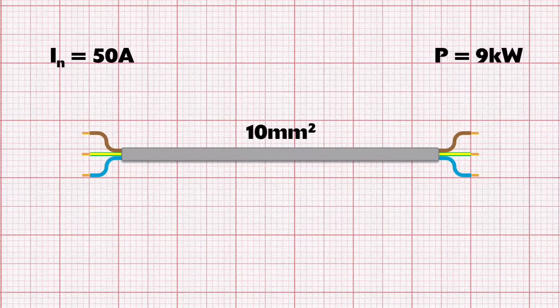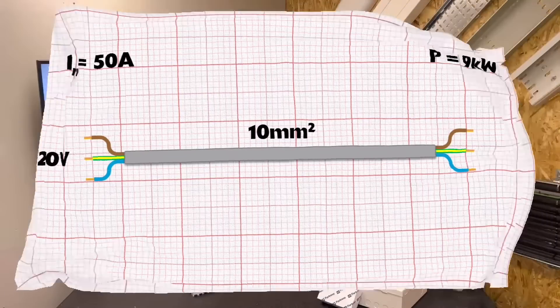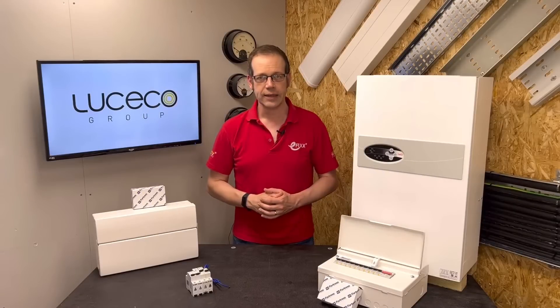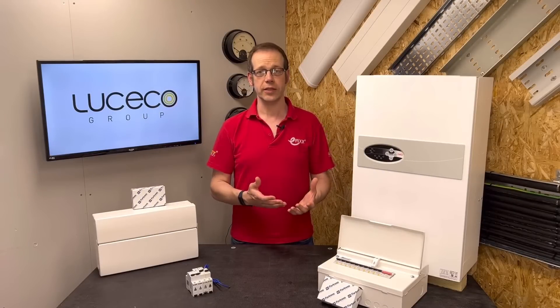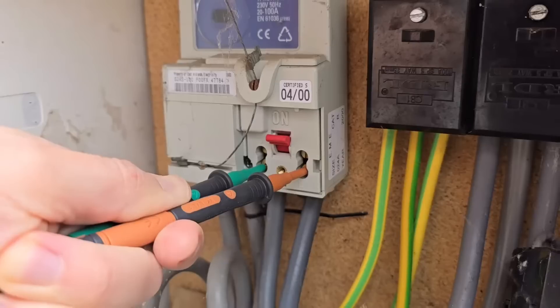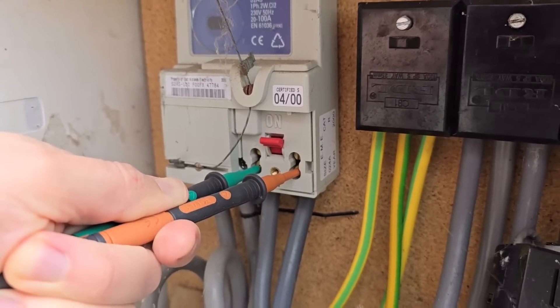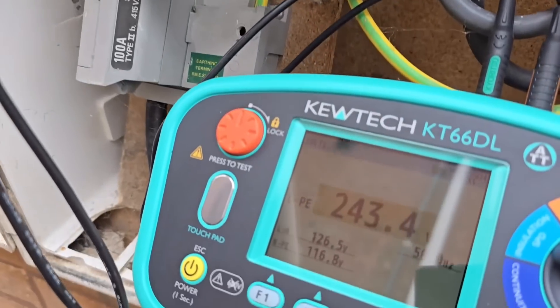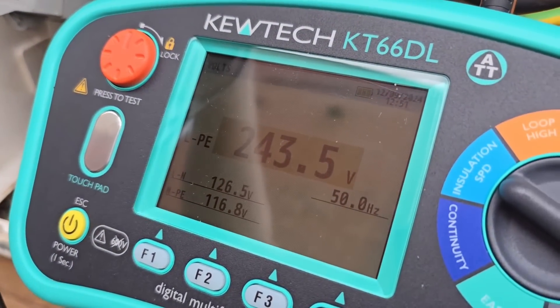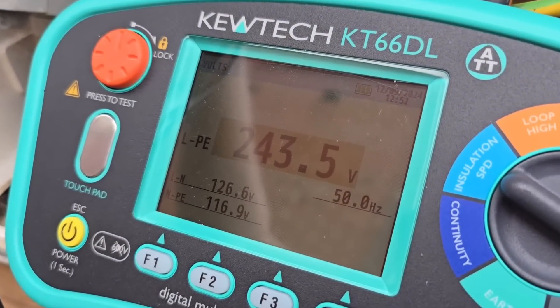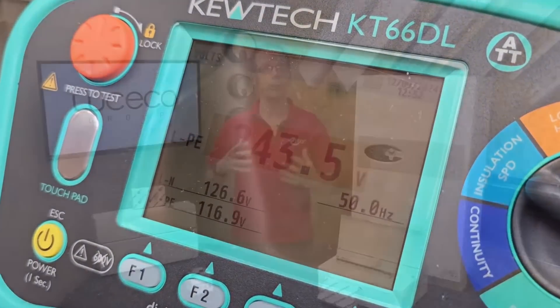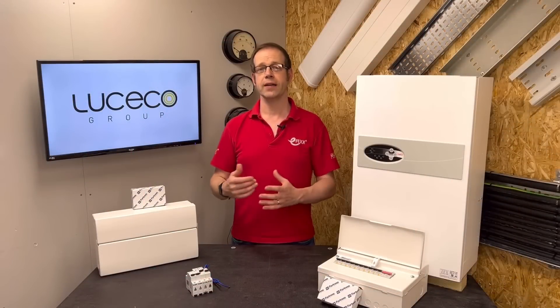Ask any electrician, apprentice, or someone vaguely connected to the electrical industry, and they'll tell you that the single phase voltage is 230 volts in the UK. This is correct in that it's the nominal voltage — the value that we aim to have delivered to properties — but in reality, it can be higher or lower when it arrives at our installation from the DNO, and it will also vary within the property depending on a number of factors.